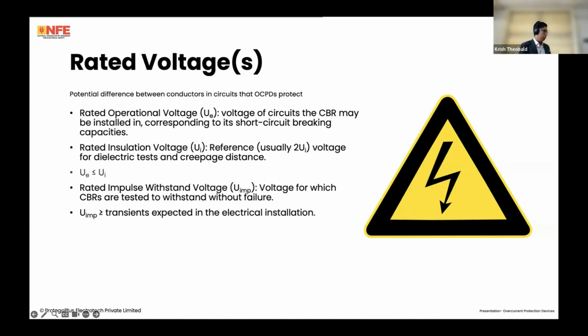So for instance, just one moment. I've got an MCCB here with me, and it says for 220 to 240 volts, it has an ultimate breaking capacity of 35 kiloamps. For 380 to 415 volts, it has an ultimate breaking capacity of 25 kiloamps. And for 660 to 690 volts, it has an ultimate breaking capacity of 6 kiloamps. So that's how these are generally defined.